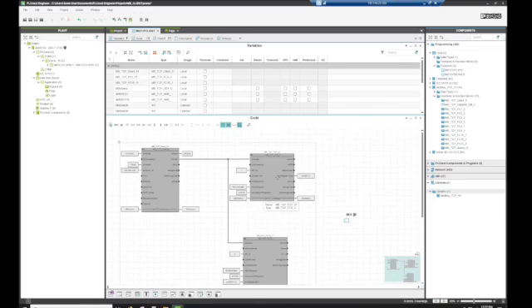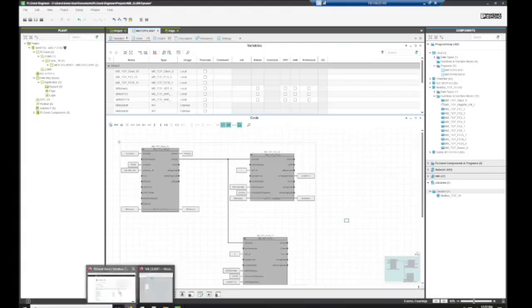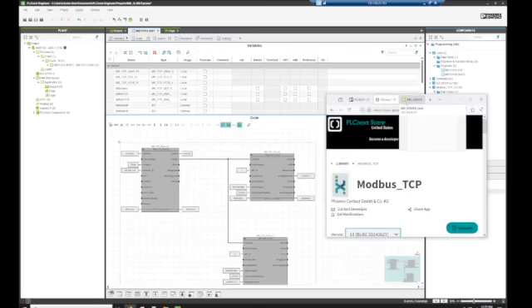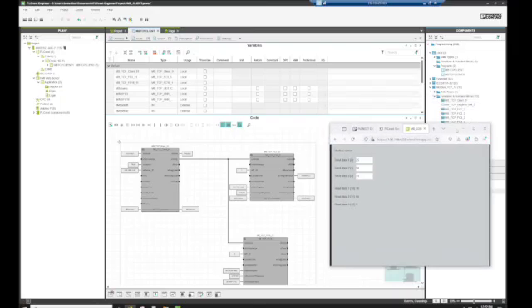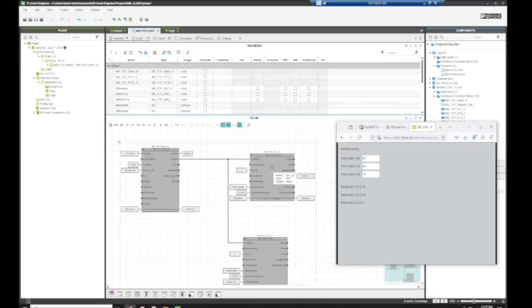Our start register: now this is where you'd have to normally pull out a manual or a data sheet on the sensor that you're working on. But in this instance I already have a server block already started and I was actually smart enough this time to put the registers that I'd like to use. So in this case we are going to a function code 3, reads holding registers. So if we'll look, the Modbus server is sending us data on registers 0, 1, and 2.